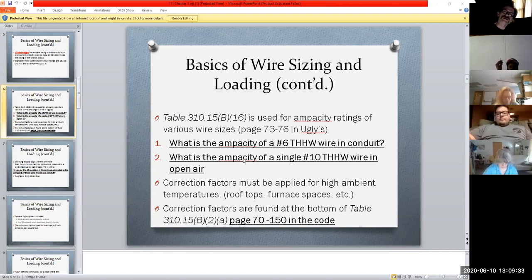In this case, you have a THHW, and the W indicates wet. That means this wire is capable of operating in a wet environment. So it's thermal high heat with a wet rating. Otherwise, you'll see a THHN, which is not meant for wet. It just means it has a nylon insulation to it. So THHN and THHW are probably the two most common nylon-insulated types you'll have involved in home wiring.